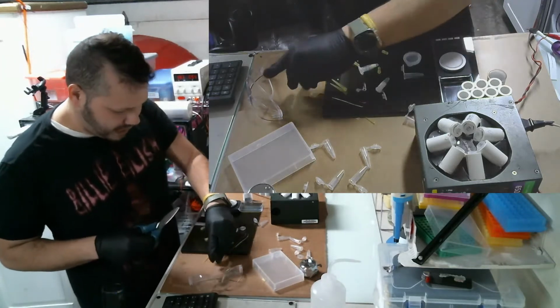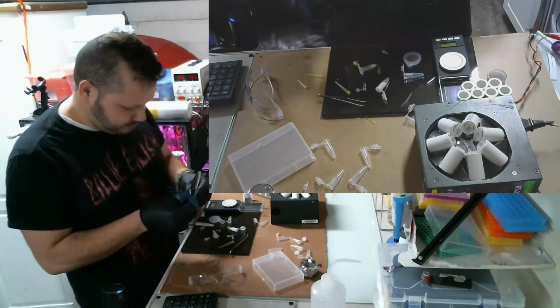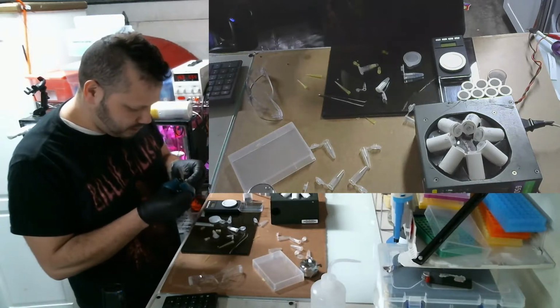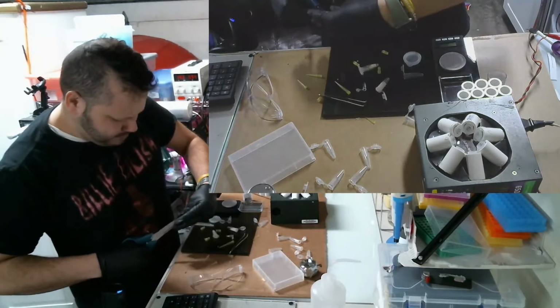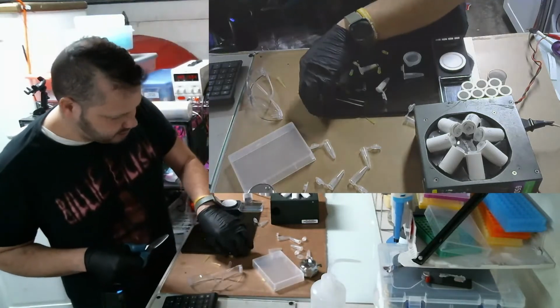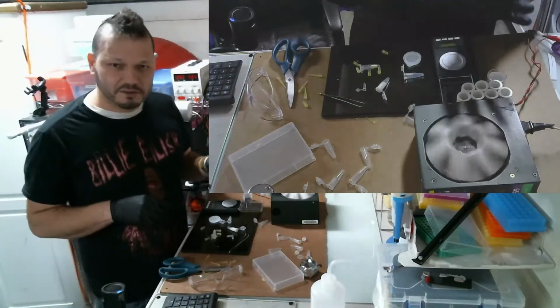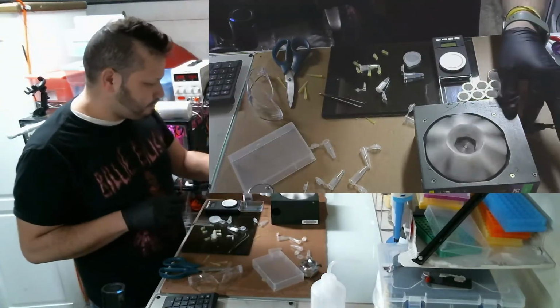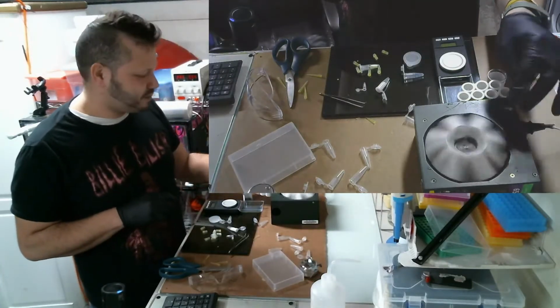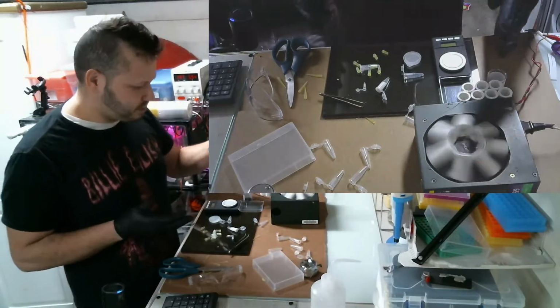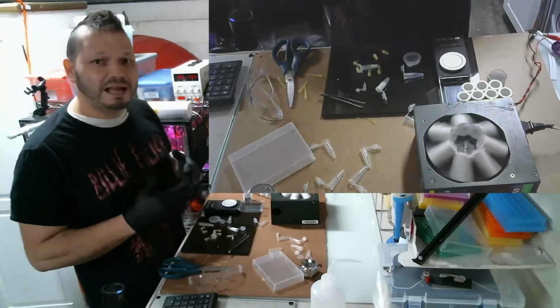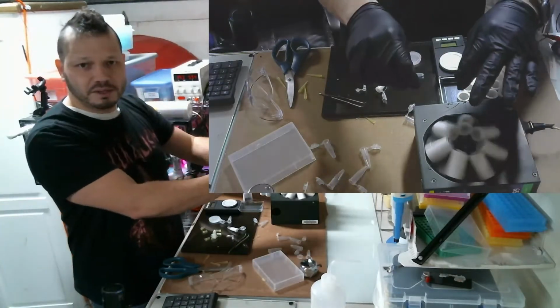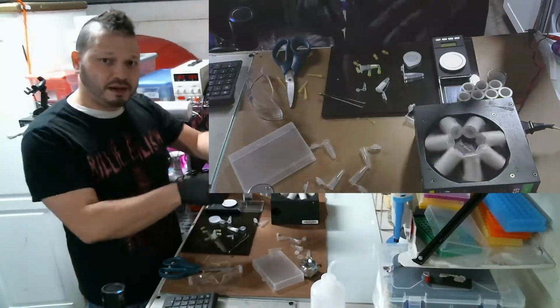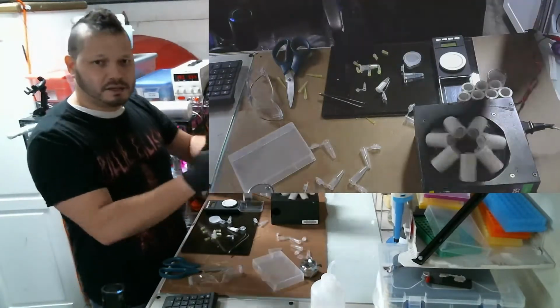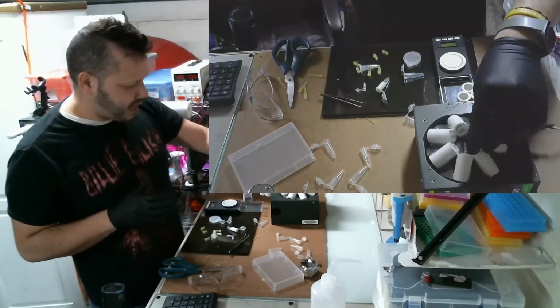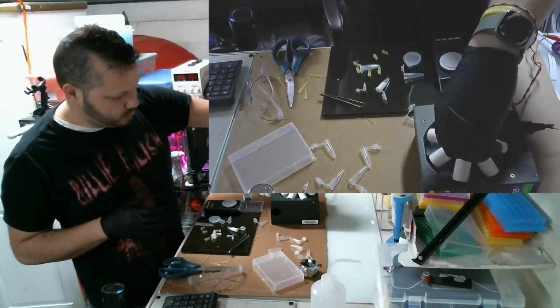When you're trying to build a home lab, you have to find out where you can save money and still have the same quality of research capability. Now, in the case of a centrifuge, you have to make sure it's balanced. One of the issues with this centrifuge, however, is that it can hold an odd number of tubes. It holds 7. So there's no way to just balance it with 2. Usually with centrifuges, as long as you have the same size on each side, you're good. So instead, I have these tubes in here which act as a balance.